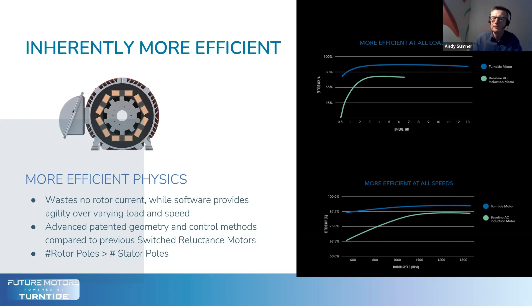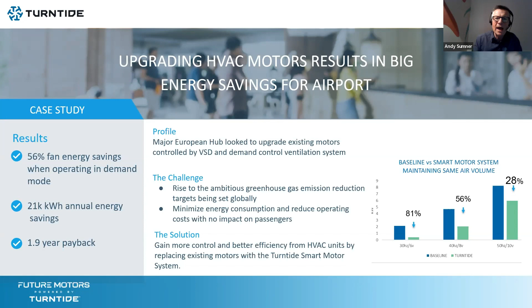To highlight that in a real life example, this is a large international airport based in the UK that uses demand control, so the motors speed up and down based on CO2 and footfall. As the motor slows down, you can see we move from a like for like 50 hertz full speed saving of 28%, right down to an 81% saving when you slow that motor down to only 30 hertz.